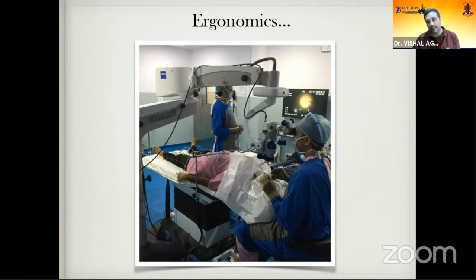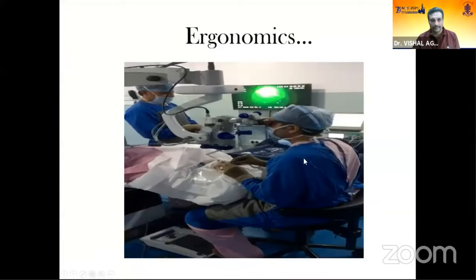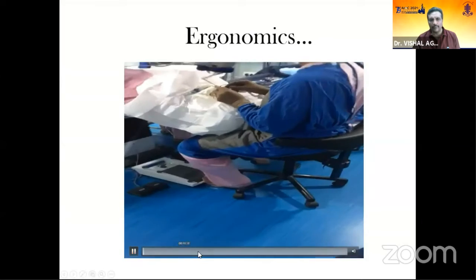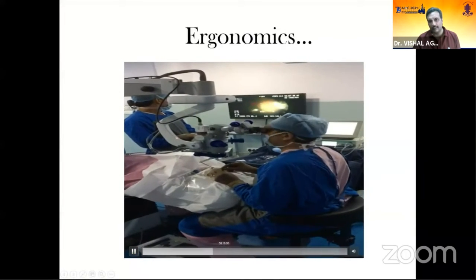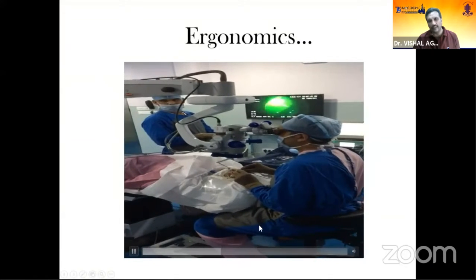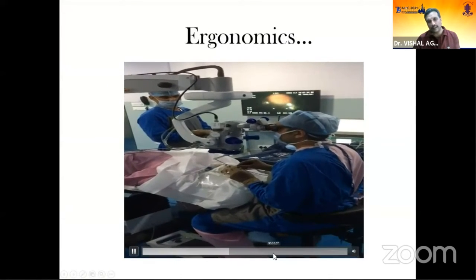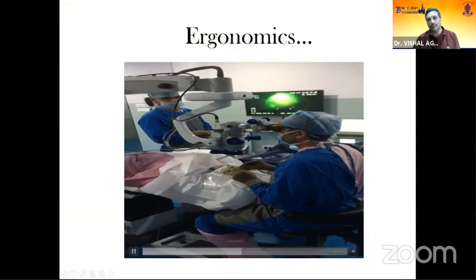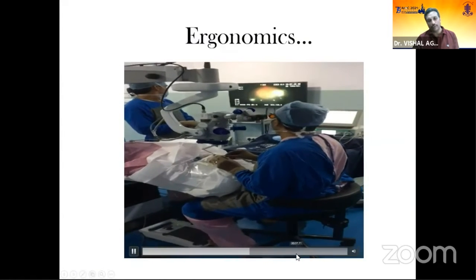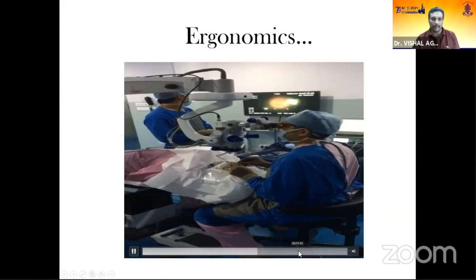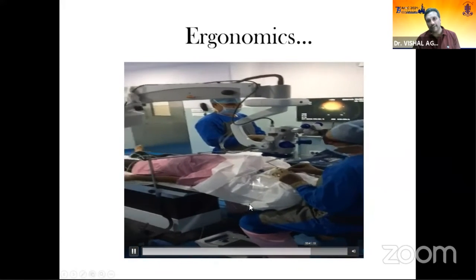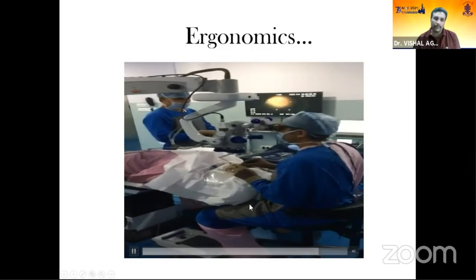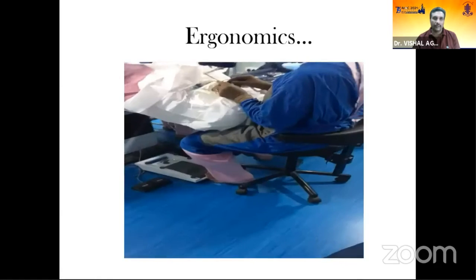The routine setup has the screen to the side, not in front, so that if you need to check picture quality you just do a head tilt. This is shown in a small video of me operating. If you place the screen in front, the microscope body gets in the way and you have to tilt your whole body to see the screen, which is uncomfortable and can disturb your surgical maneuvers.